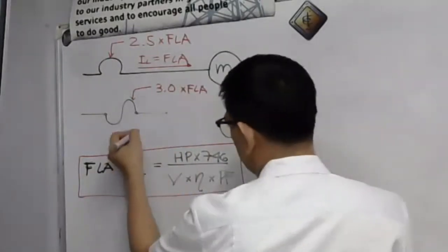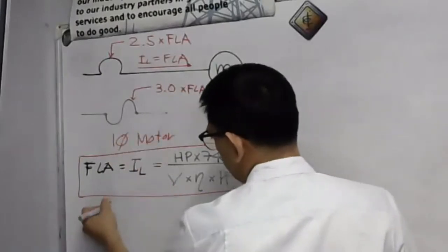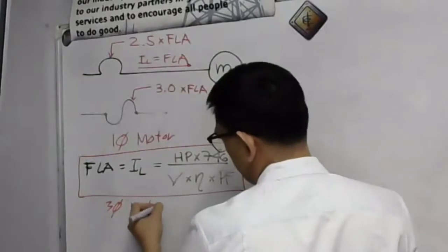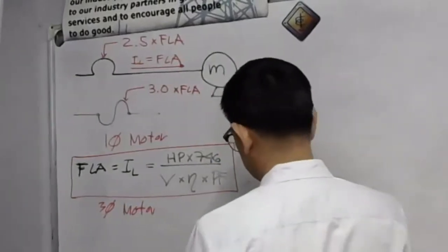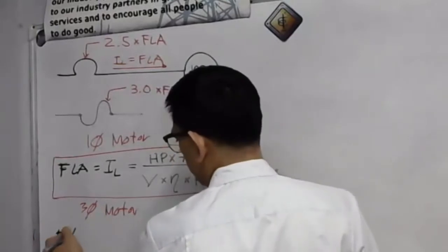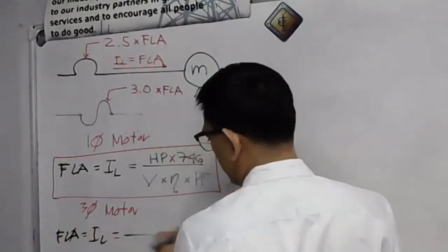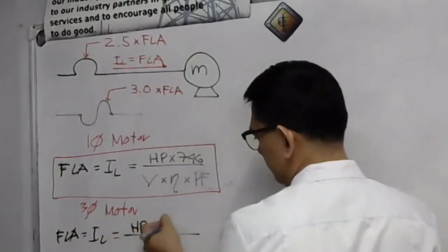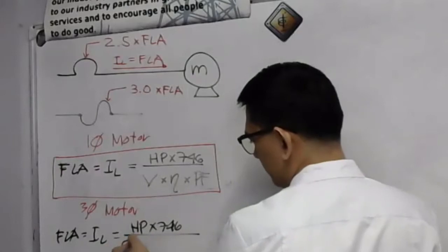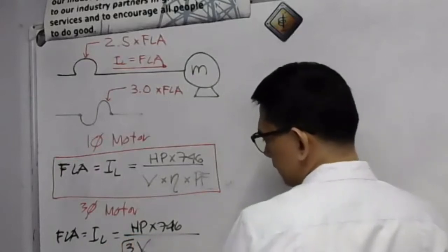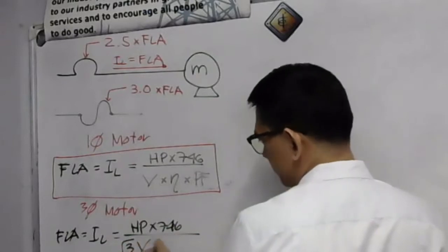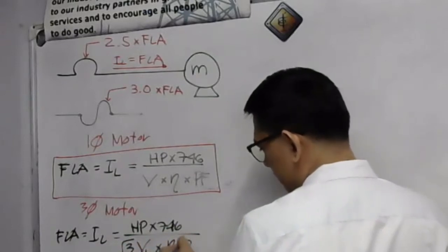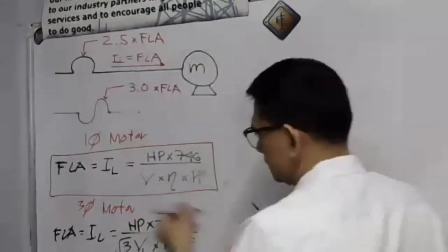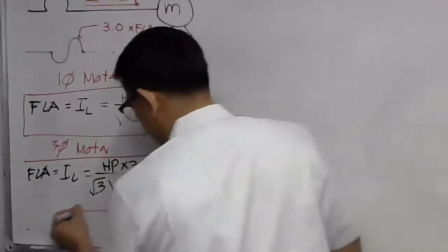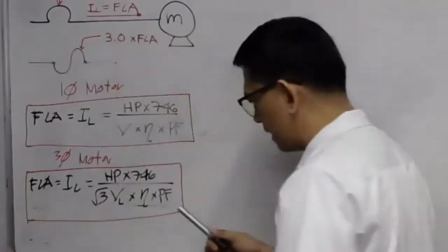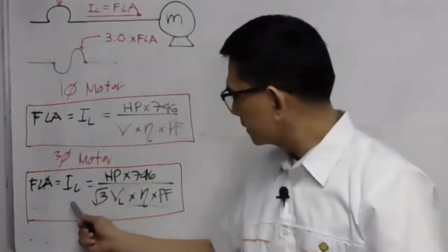For the case of the 3-phase motor, our full load ampere, which is our line current, is equal to the horsepower times 746 divided by square root of 3 multiplied by the line voltage, to be specific, multiplied by the efficiency multiplied by the power factor. So this is our formula in getting the line current. Ito po ang ating formula.